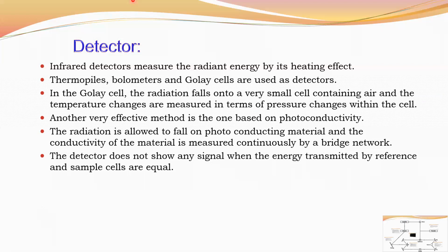Only alternatively it passes the reference beam and the sample beam. So after reaching the detector, the beams reach it one by one. It comes to the detector alternatively.